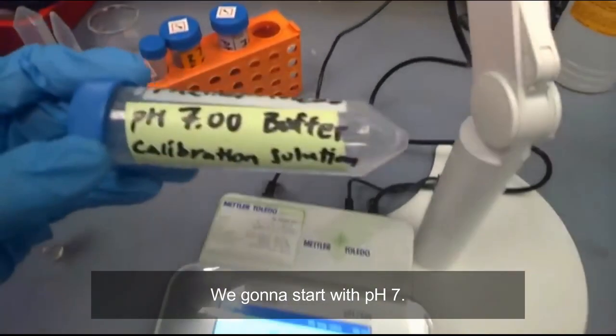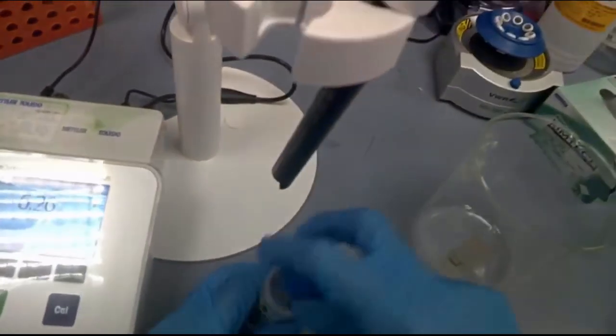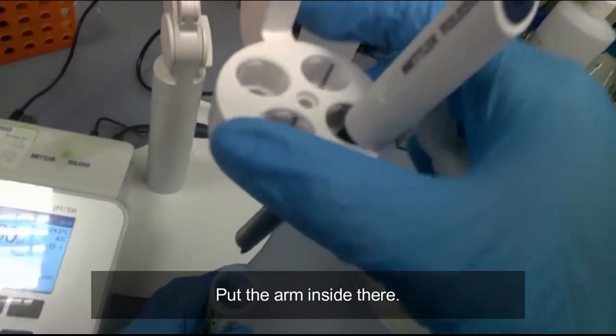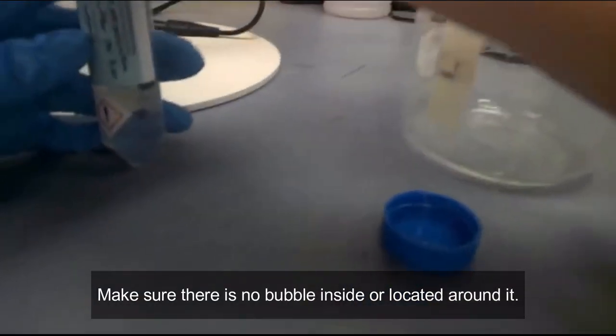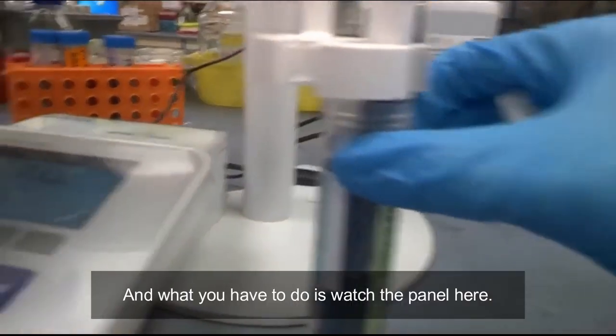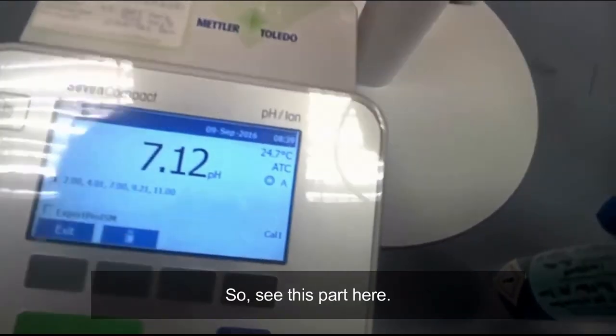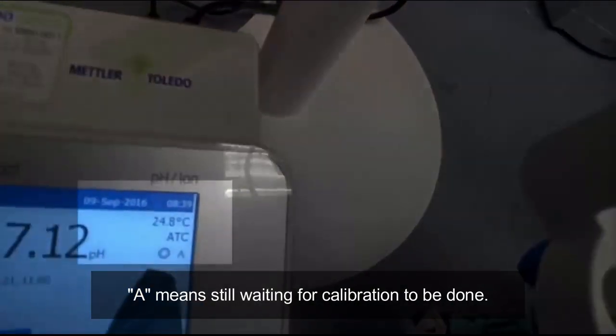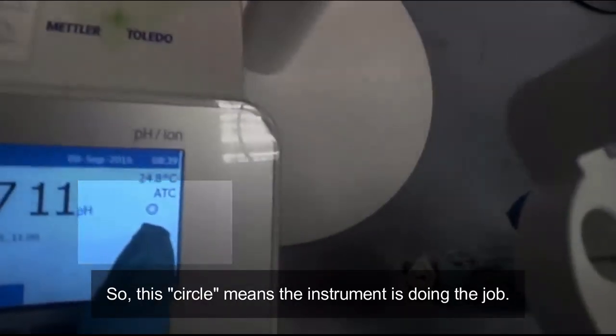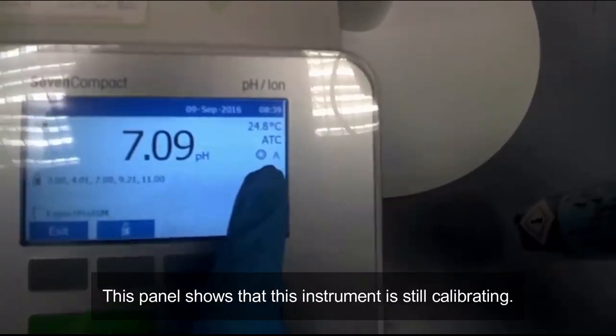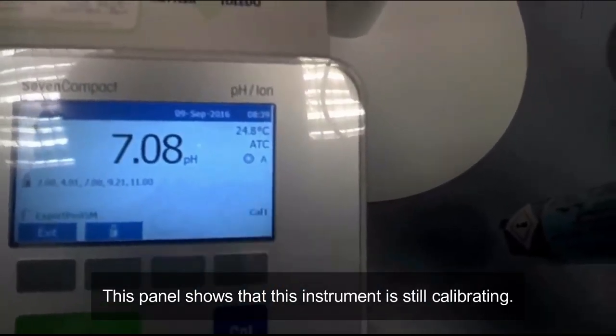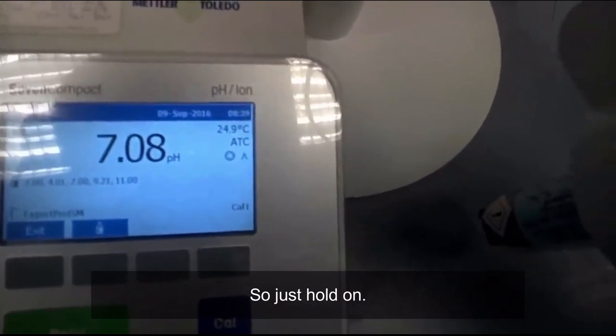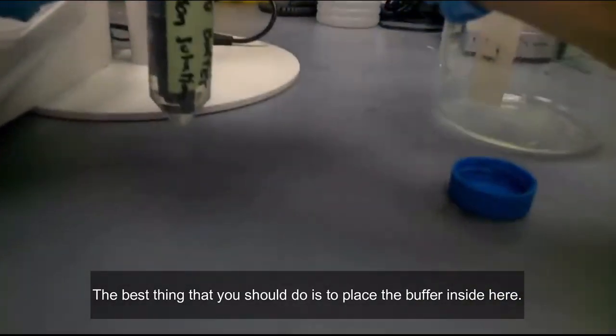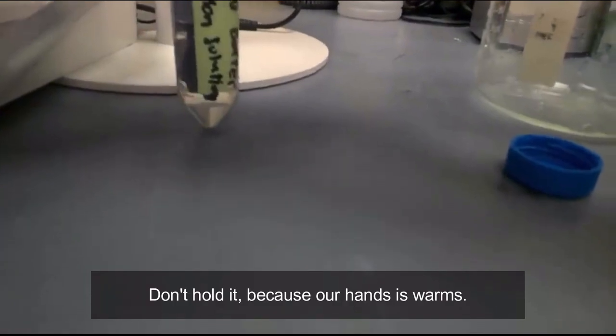We're going to start with pH 7, so here is the buffer. Put the arm inside there. When you place the probe inside the sample, make sure there is no bubble inside or around it. What you have to do is watch the panel here. See this part here? A means still waiting for calibration to be done. So this circle means the instrument is doing the job. So this panel shows that this instrument is still calibrating. So just hold on. The best thing that you should do is to place the buffer inside here.